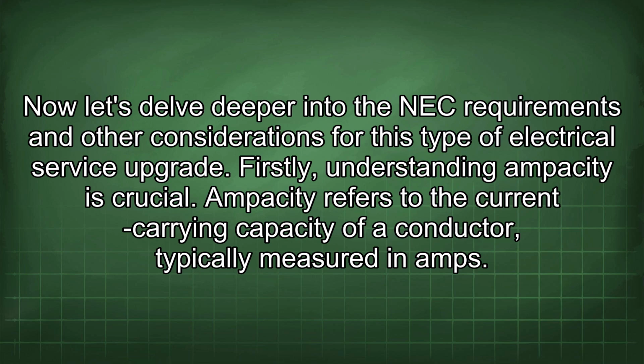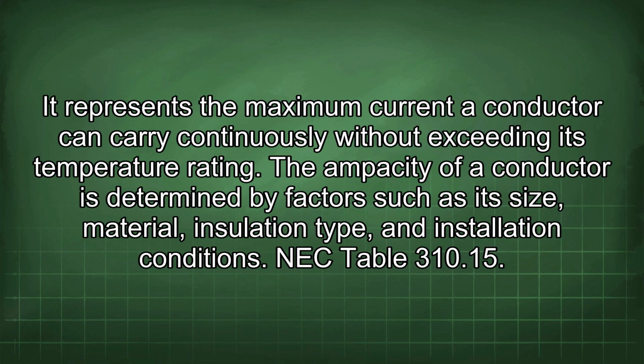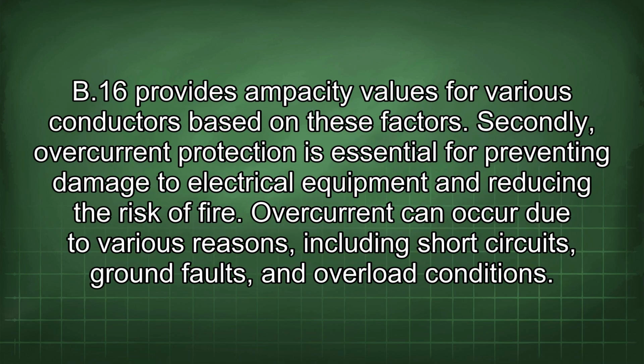Firstly, understanding ampacity is crucial. Ampacity refers to the current carrying capacity of a conductor, typically measured in amps. It represents the maximum current a conductor can carry continuously without exceeding its temperature rating. The ampacity of a conductor is determined by factors such as its size, material, insulation type, and installation conditions. NEC Table 310.15(B)(16) provides ampacity values for various conductors based on these factors.